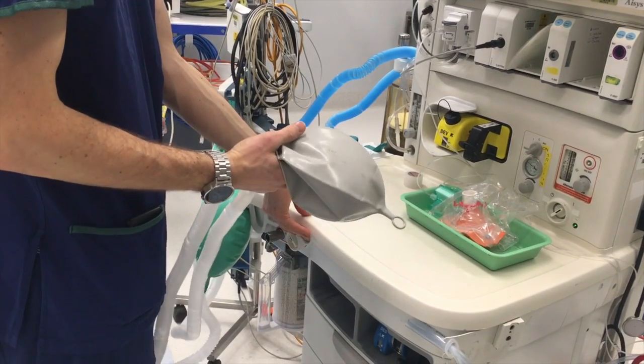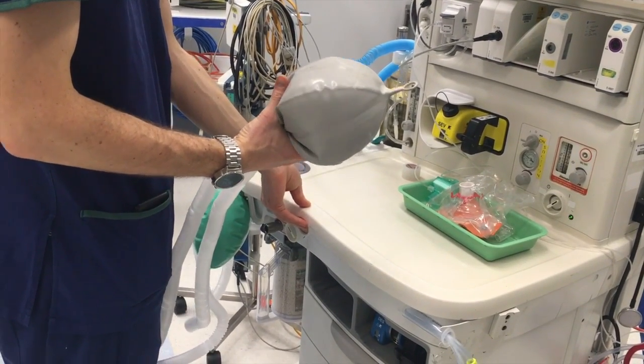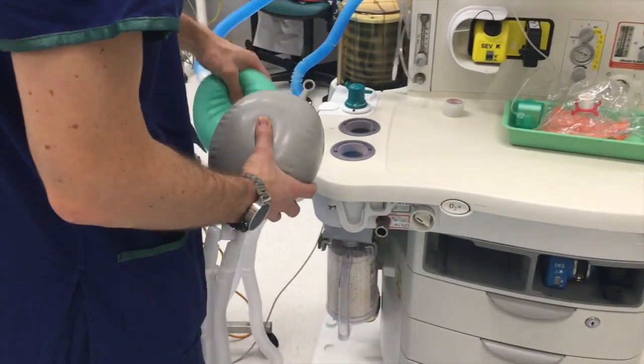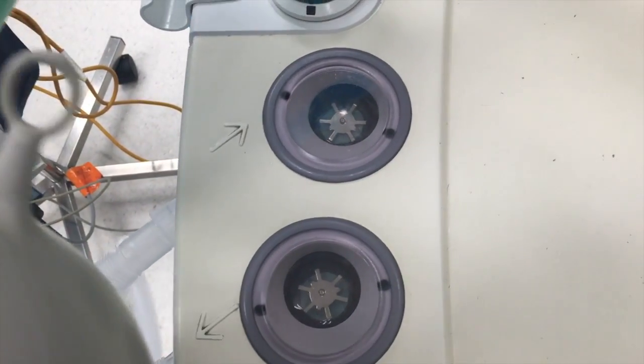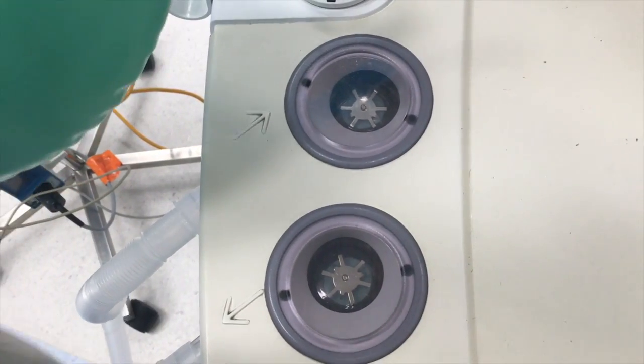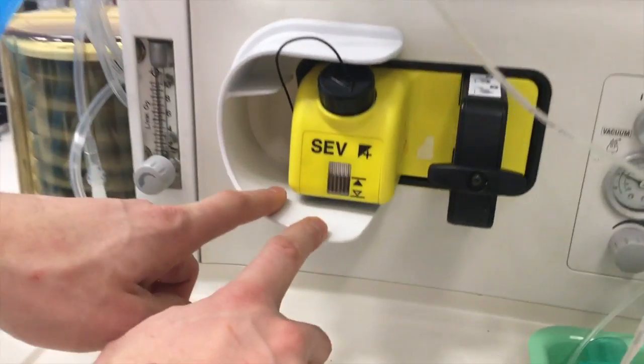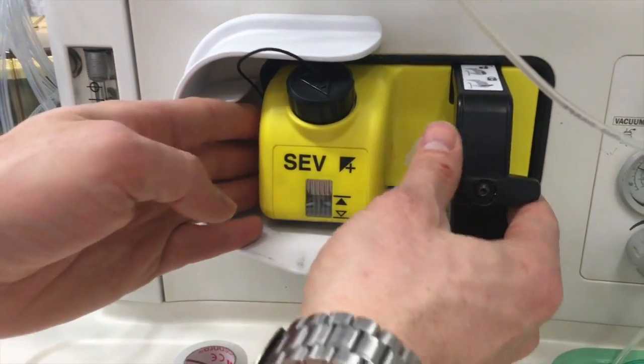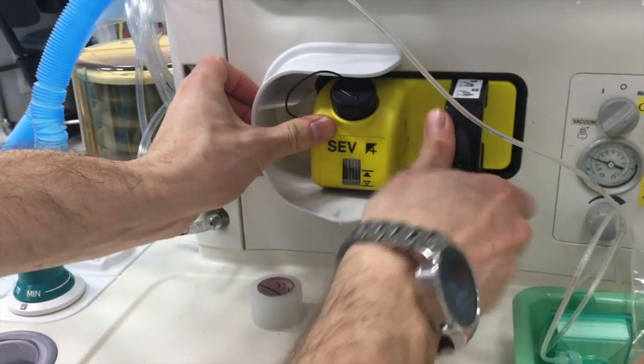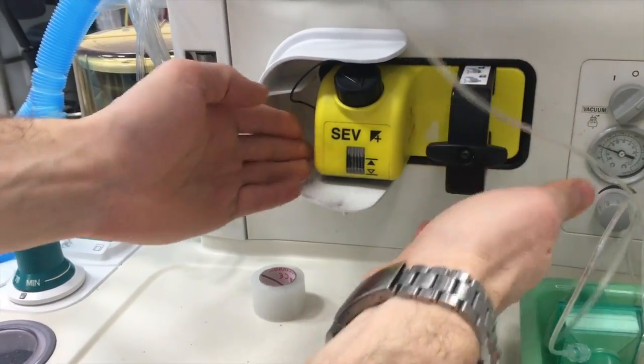Fill the bags using the oxygen flush at the front of the machine. With the flow still at 5 litres, ventilate manually by squeezing the bags and check that the unidirectional valves are opening and closing in sequence. Next, check that the vaporizer has an adequate volatile level and is firmly and correctly positioned and locked in.